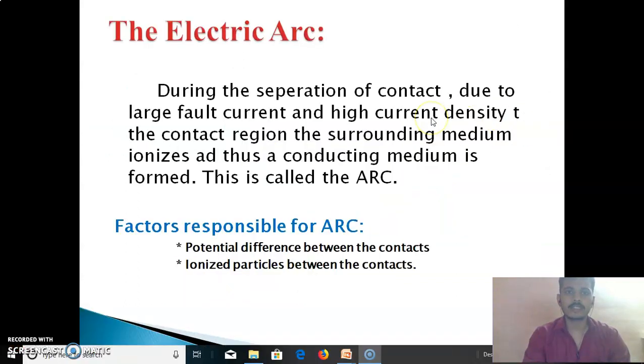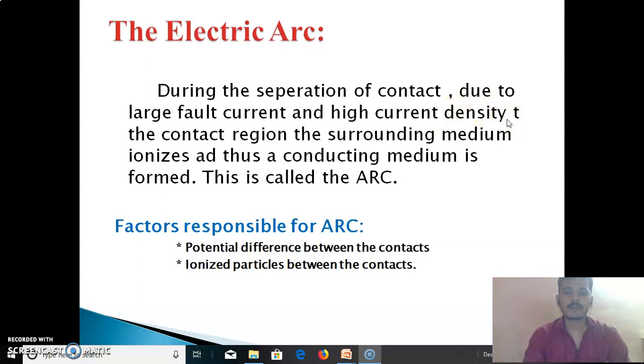Next, we see the electric arc. During the separation of contacts, due to large fault current and high current density in the contact region, the surrounding medium ionizes and a conducting medium is formed. This is called the arc. The two factors responsible for arc are: first, the potential difference between the contacts, and second, the ionized particles between the contacts.